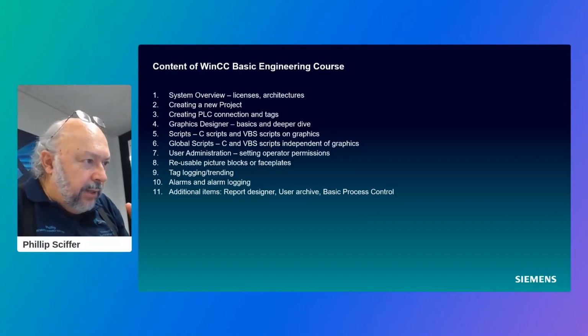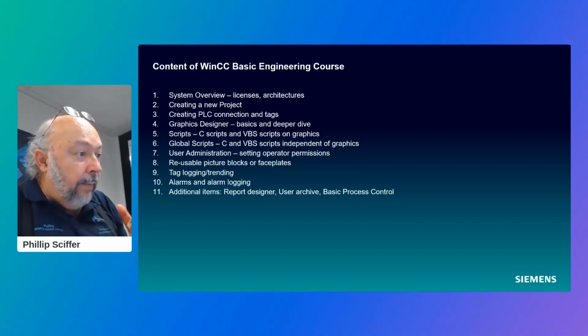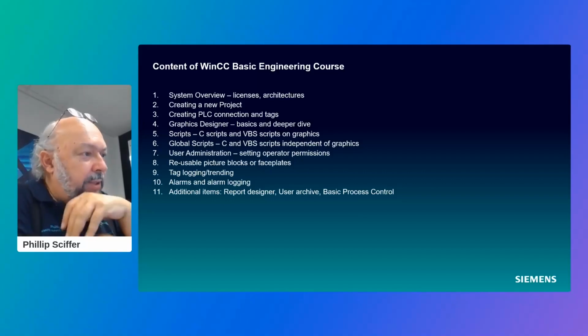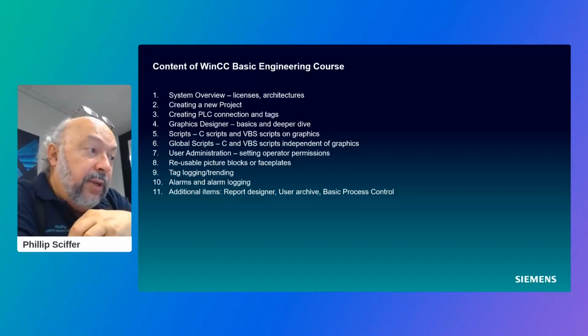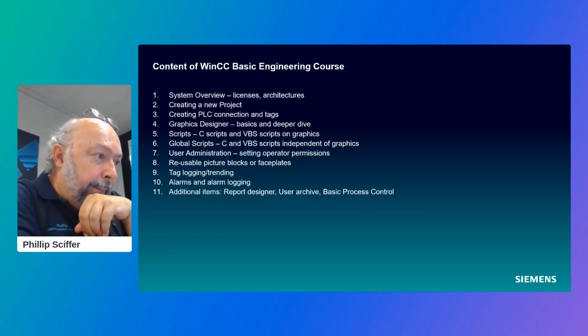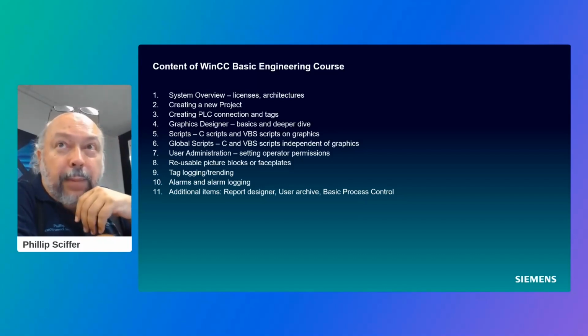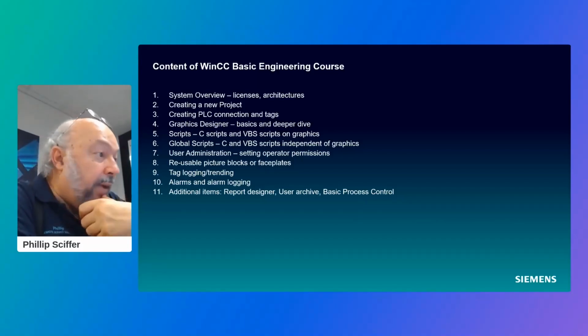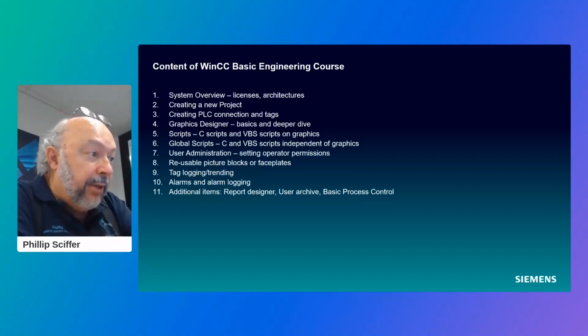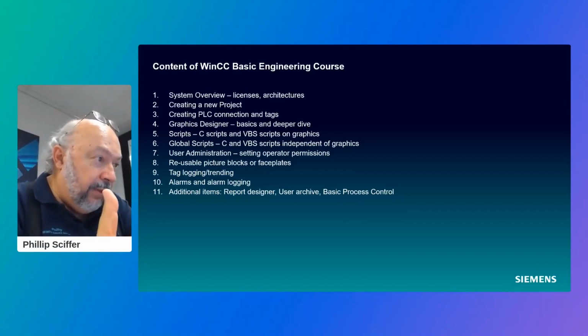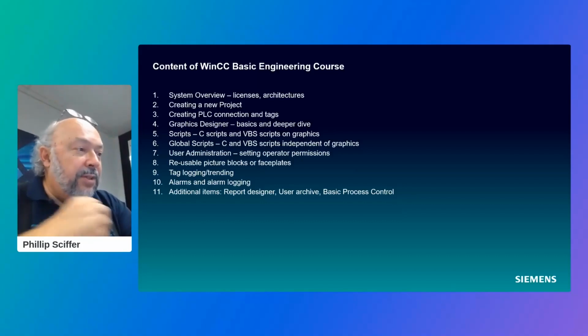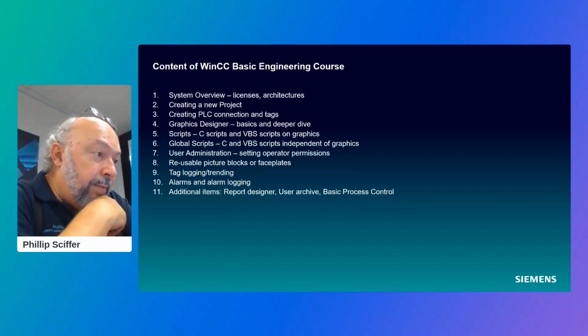We look at user administration, similar to what we had with the PCS7 case. We look at making reusable picture blocks, or faceplates. A WinCC faceplate is a bit different from a PCS7 faceplate, but we look at how they can be configured to efficiently engineer graphics that can be reused for multiple instances of the same thing. So if you've got a motor block in the PLC, you can make one graphic showing what's happening with the motor, then call that same graphic for lots of different motors. You only have to do the graphics once.